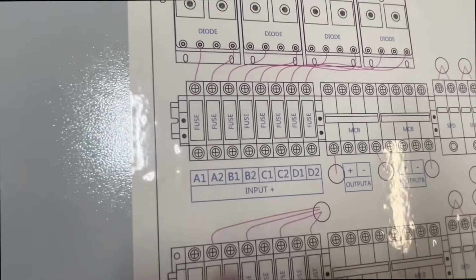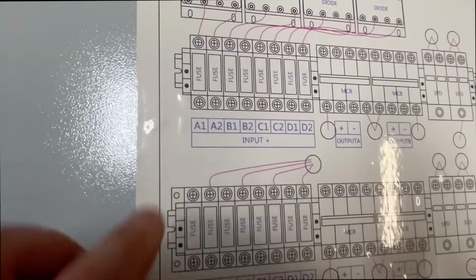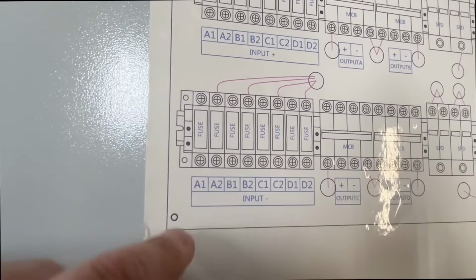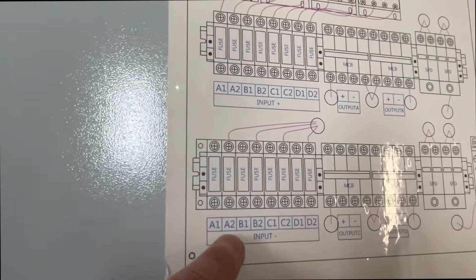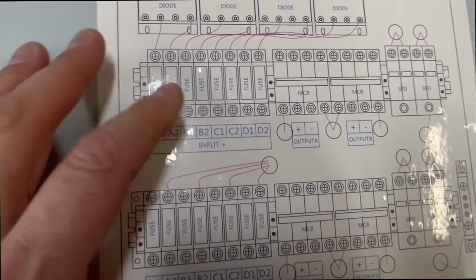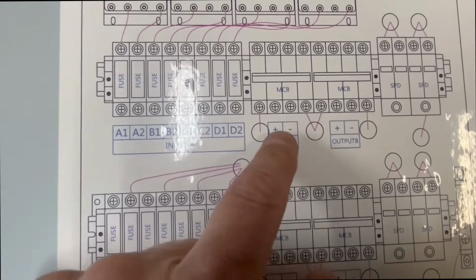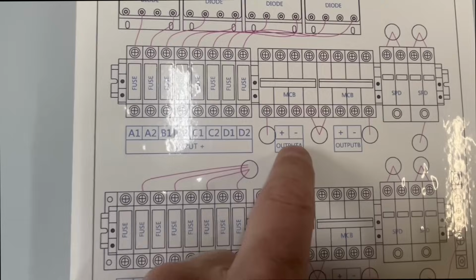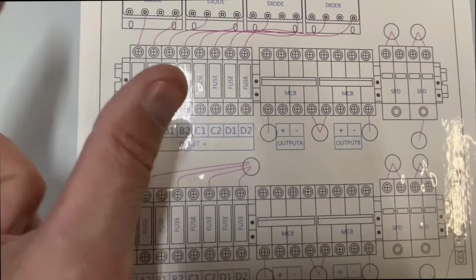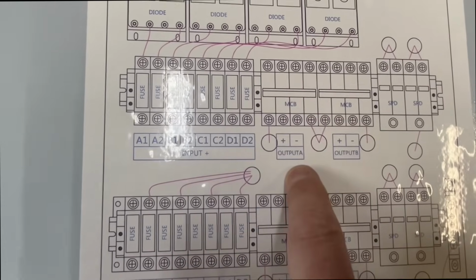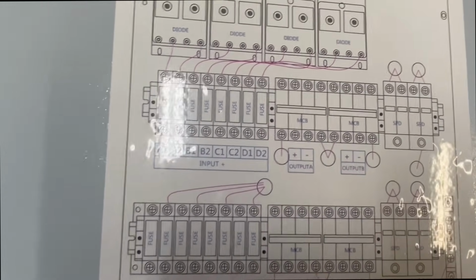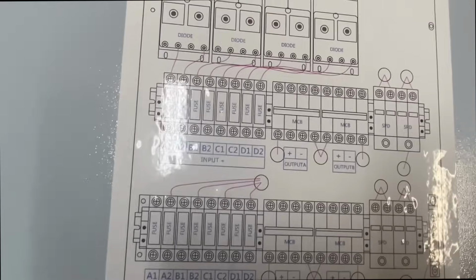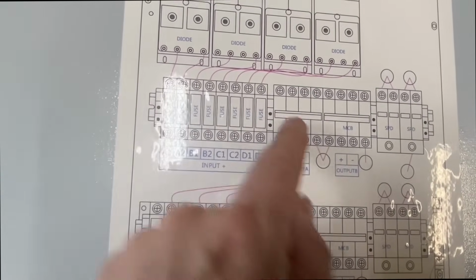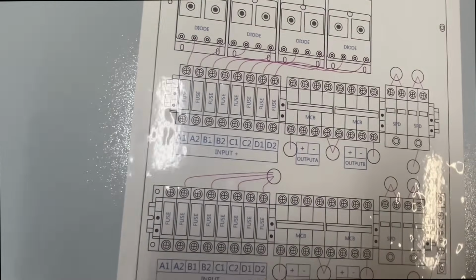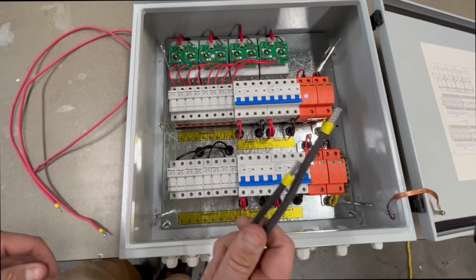So coming back to the map here, we have A1 and A2, and that is going to be the first string. Up here is A1, A2 positive. Down here is A1, A2 negative. And once those two strings are combined, you'll see they're going to output with A output right here. So you've got A1 and A2 tied together, and then it's going to come out right here. And then same thing with the negative. Just like I showed you on that Polaris splice, you're just combining two strings and making them one coming out, doubling that amperage.